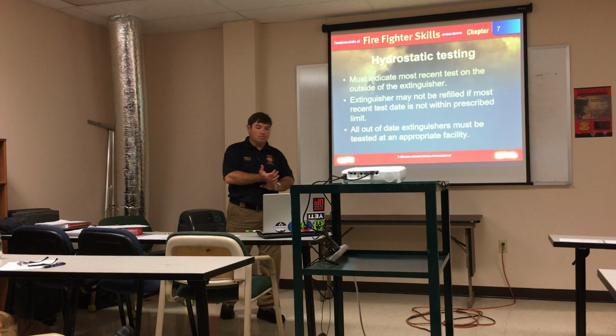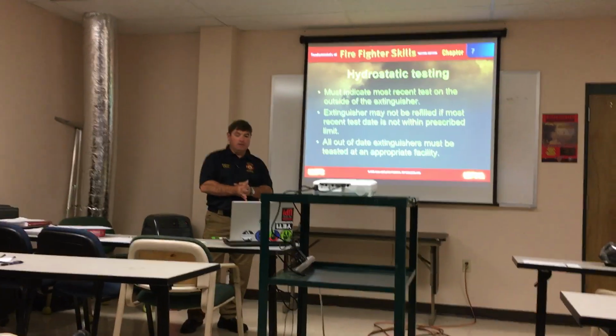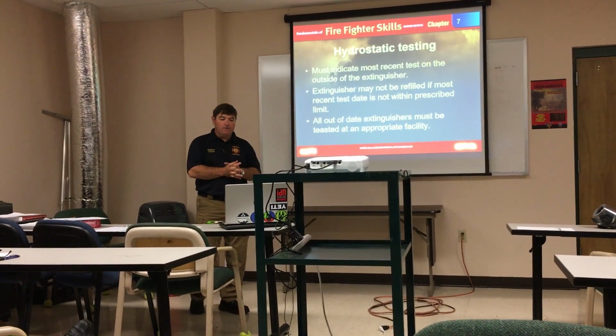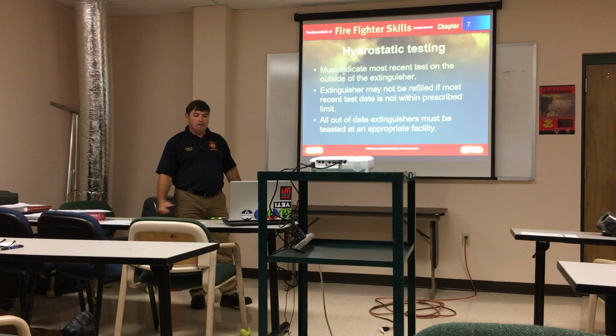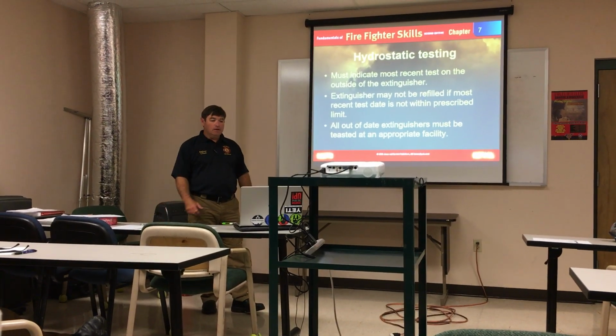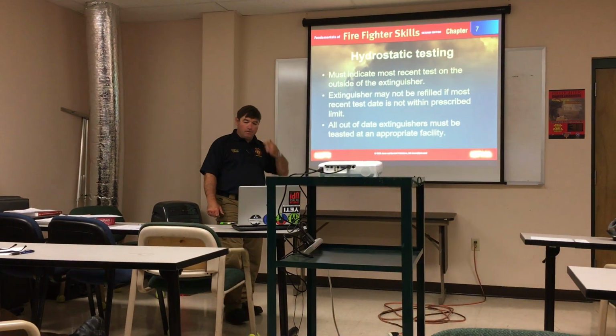They should have a marking on the outside of the extinguisher that indicates the most recent test. The extinguisher may not be refilled if the most recent test date is not within prescribed limits. All out-of-date extinguishers must be tested at an appropriate facility.